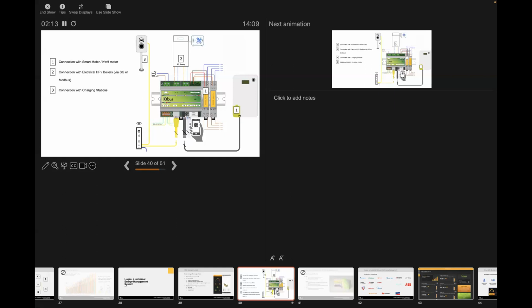You also want to connect your energy management system with the charging stations for your vehicles. How do you speak with these? It's mostly via TCP/IP protocol, used by a lot of charging station manufacturers, mostly Modbus TCP/IP. Some use serial Modbus as well, but in our experience 90% uses Modbus TCP/IP. There are protocols being developed, OCPP etc., but they're not really at the level where they're used massively for the time being.